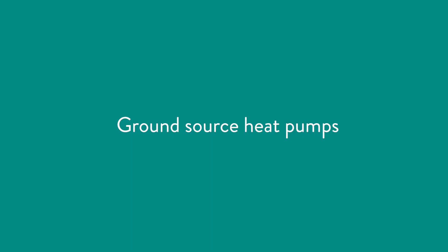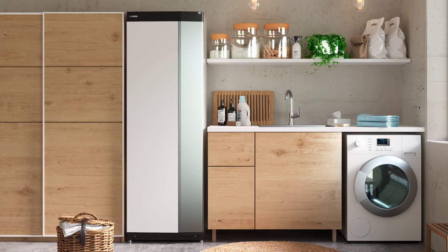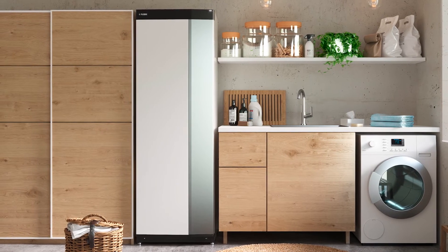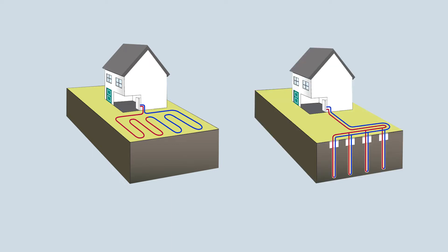There's potential for government grants to bring this cost down by up to £5,000. This is a ground source heat pump. They work by drawing warmth — indirect solar energy that's stored within the ground. They're similar in size to an upright fridge freezer and the heat pump, domestic hot water cylinder and buffer tank are all installed inside the property, usually within a dedicated plant room. The collectors that extract the solar energy from the ground are outside, which would either be ground loops where you bury the collected pipework around 1.2 metres below the ground, or boreholes where you drop collectors down a vertically drilled hole.